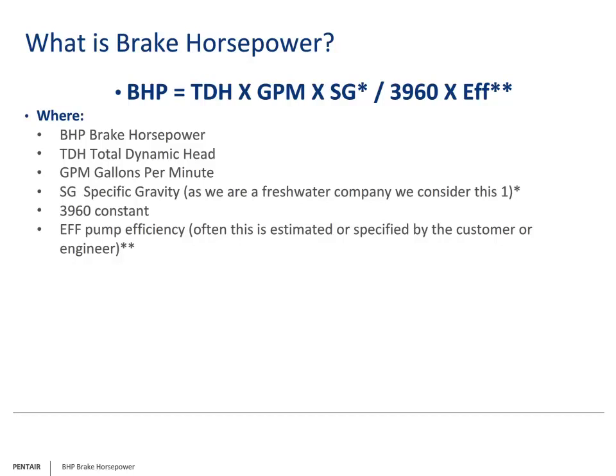You also need to know the horsepower constant 3960. And finally, the efficiency of the pump. How do you know the efficiency of the pump? Well, often the efficiency is dictated by the customer, for example an engineer, or an efficiency of your own determination. For this discussion we will be using 81%.